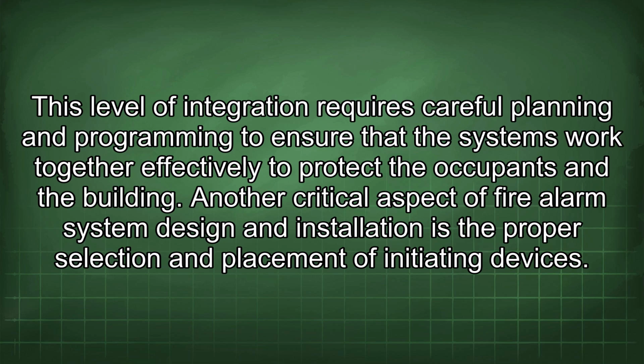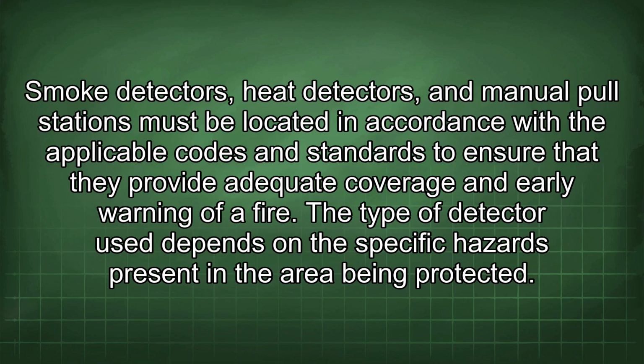This level of integration requires careful planning and programming to ensure that the systems work together effectively to protect the occupants and the building. Another critical aspect of fire alarm system design and installation is the proper selection and placement of initiating devices. Smoke detectors, heat detectors, and manual pull stations must be located in accordance with the applicable codes and standards to ensure that they provide adequate coverage and early warning of a fire. The type of detector used depends on the specific hazards present in the area being protected.